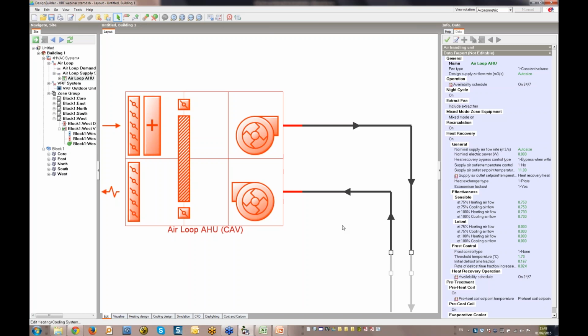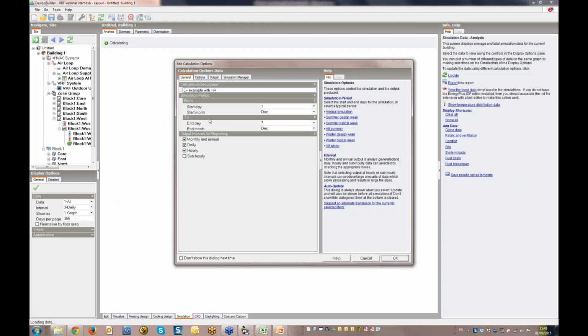I already have a result set prepared for the same Energy Plus example VRF system with heat recovery switched off. So I'll run a new simulation using the same system but with heat recovery switched on to enable direct comparison. Going to the simulation calculation options, I'll give the calculation a meaningful name and run a quick winter design week simulation generating hourly results.